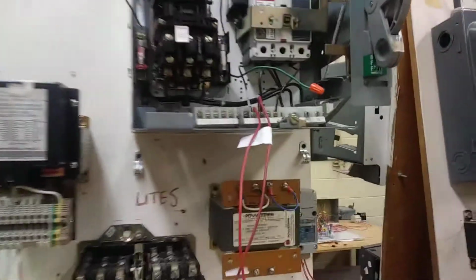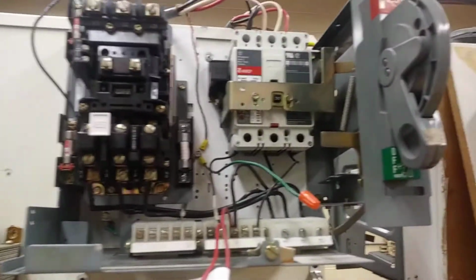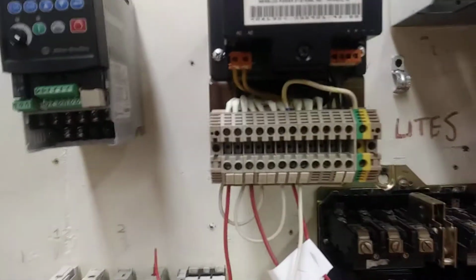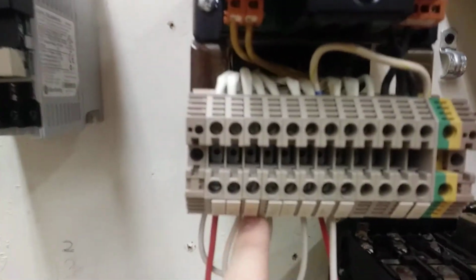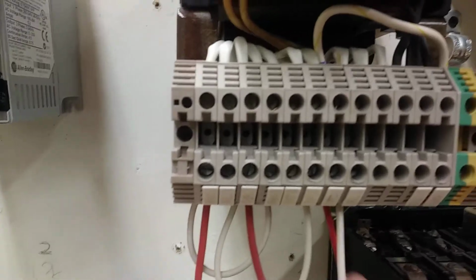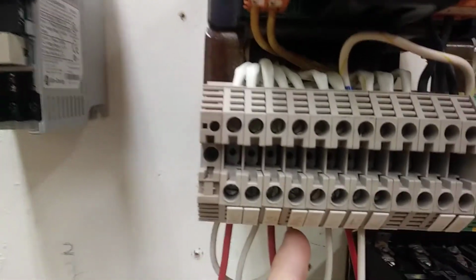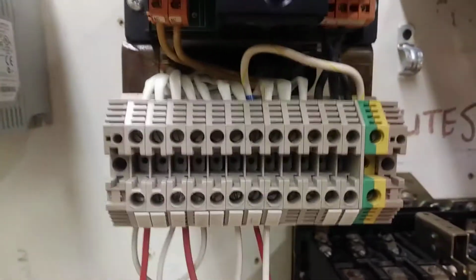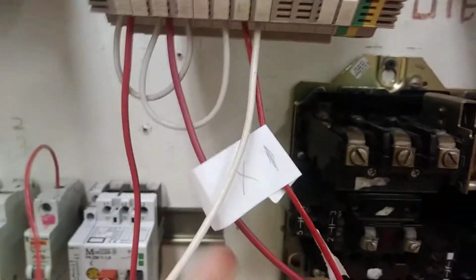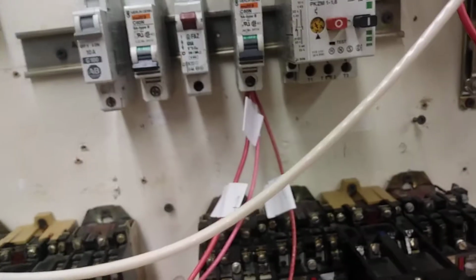So starting off, we've got our power supply, line 1 and line 2, going over to our transformer. Line 1 is connected to H1 and line 2 is connected to H3. Now H1 and H4 are connected by a jumper cable, and H3 and H6 are connected by a jumper cable. Now our X1 is connected over to our circuit breaker, and from our circuit breaker these are the three lines that are on our diagram.